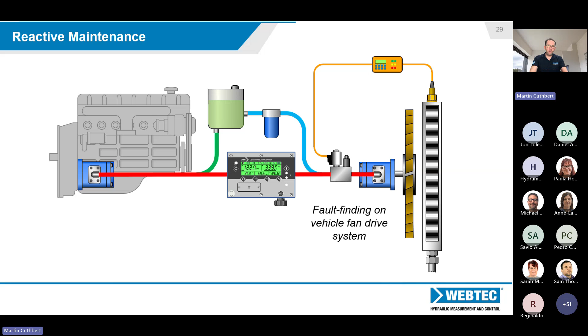So in the simple schematic you can see there, we've got the tester installed after the relief valve. At low pressure, the pump flow may appear correct. As we turn the load valve, we are forcing the pump to do more work. The pressure goes up. As the pressure goes up, we would see the flow go down. If that flow follows something closer to the red line rather than the green line, then we know that the leakage is increasing excessively and start to question whether the pump is still suitable or not, whether it's worn out.